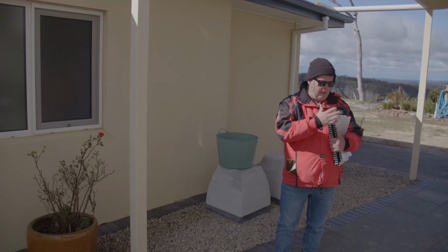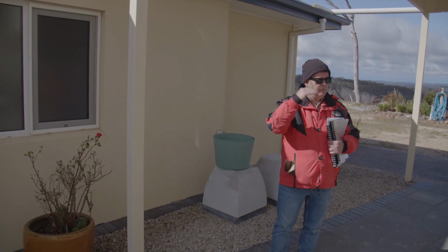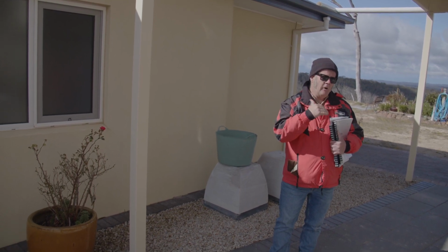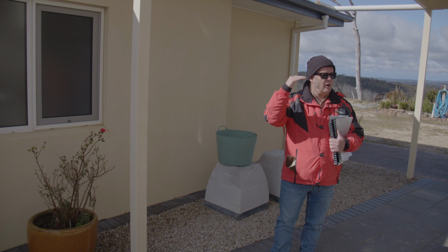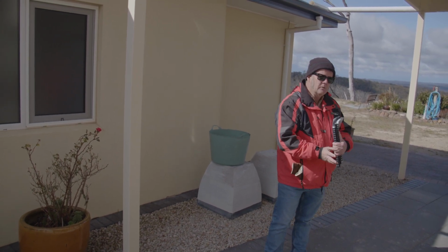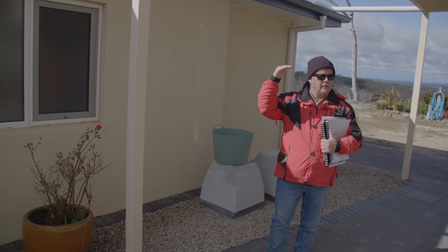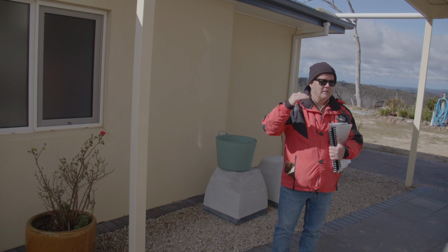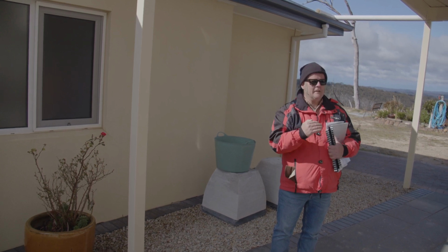So in the standards, as you go through the different levels, as it gets higher, the quality and the fire protection of the glass gets higher. The glass gets thicker. It goes from annealed glass, which is just ordinary glass, through to toughened glass and safety glass, and gets far more expensive. So flame zone windows are poisonously expensive.